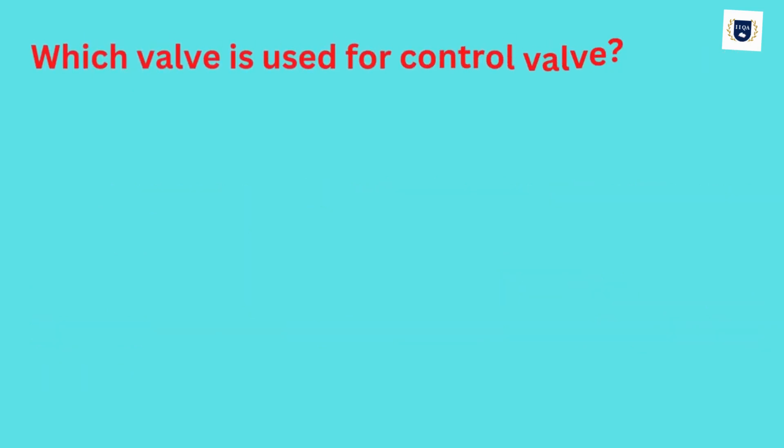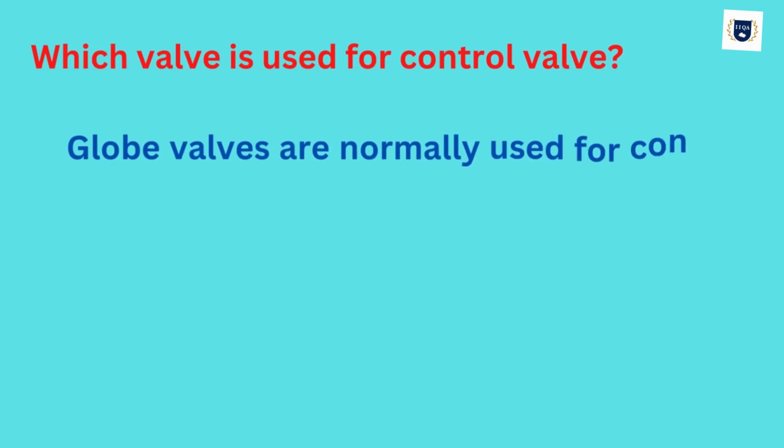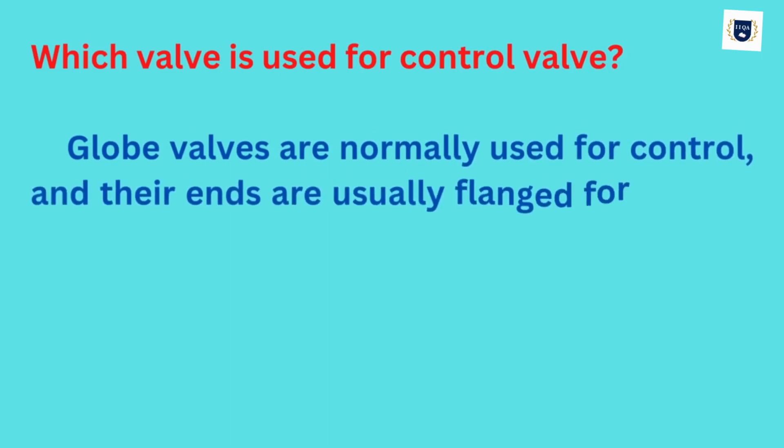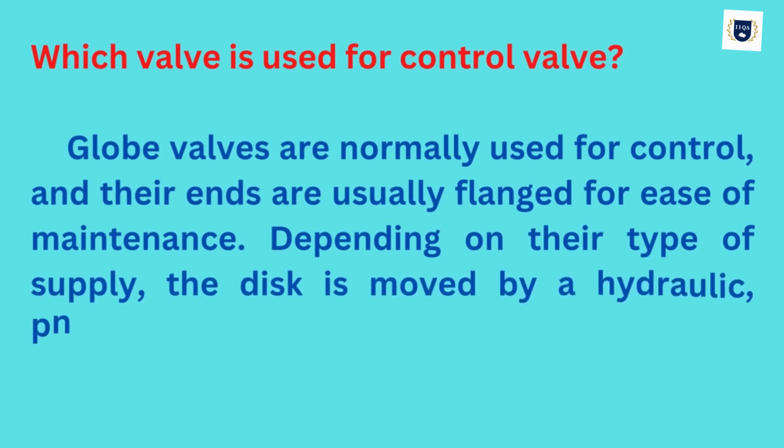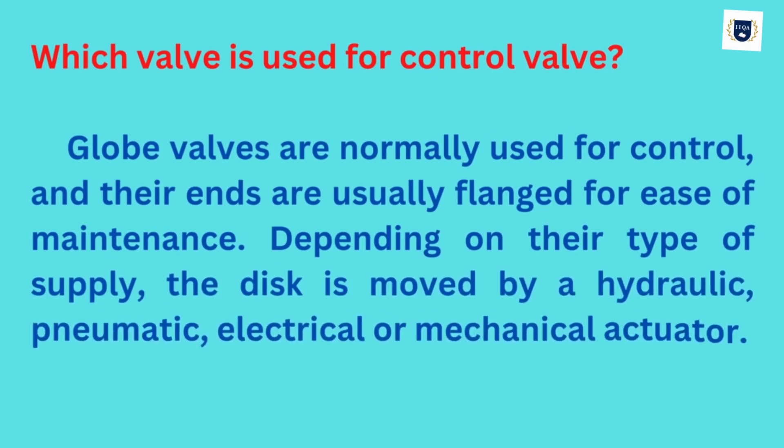Which valve is used for control valves? Globe valves are normally used for control and their ends are usually flanged for ease of maintenance. Depending on their type of supply, the disc is moved by a hydraulic, pneumatic, electrical, or mechanical actuator.